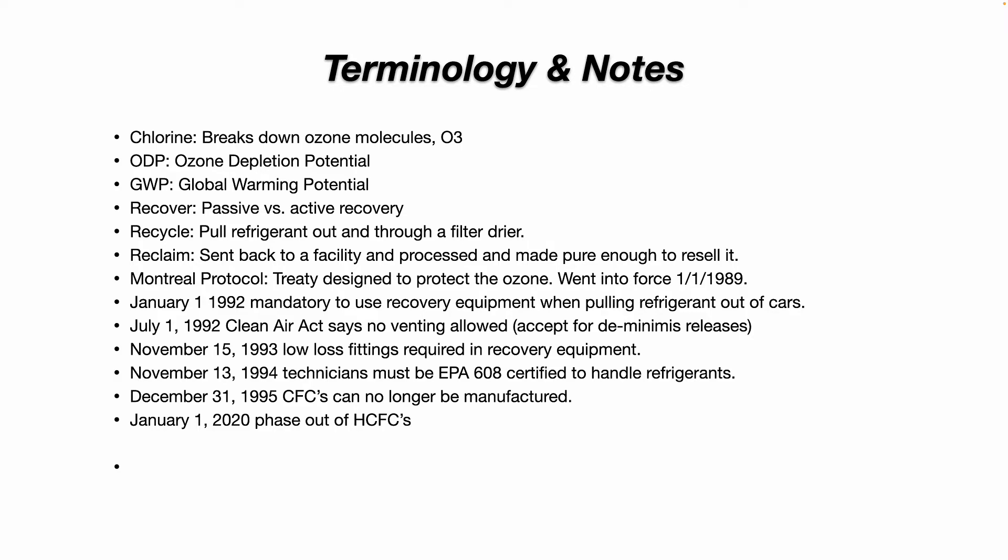A de minimis release is unintentional and unavoidable — or if you're recovering refrigerant and something fails and bursts. What is NOT de minimis is if you intentionally go up to a piece of equipment, cut the refrigerant line, and release the full charge to the atmosphere. That is illegal and will get you a fine. If someone sees you do it, they can receive a reward of up to $10,000. De minimis means accidental — you made a good-faith best effort to avoid releasing refrigerant into the atmosphere.